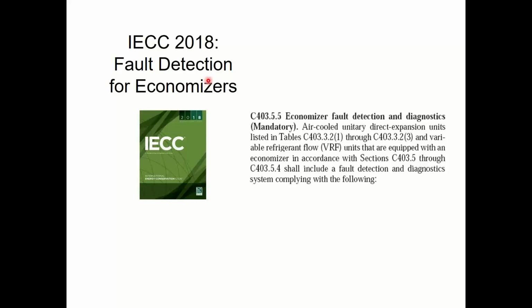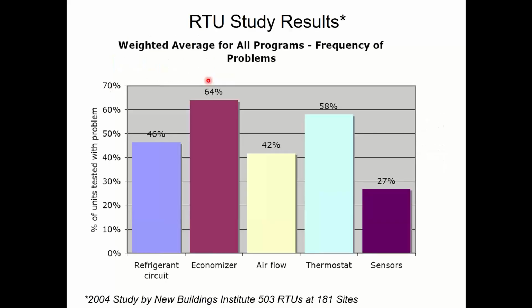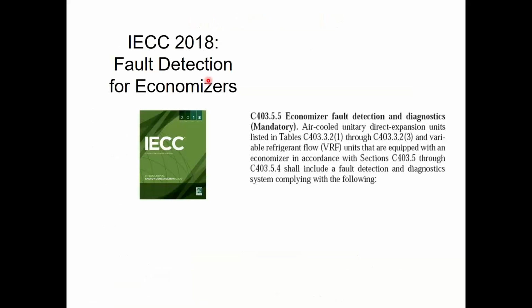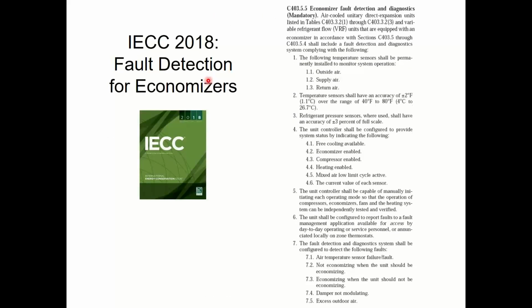The newer versions of the code coming out have even more FDD things, but economizers are the very first one to get it because economizers had this chart that said economizers suck. You guys are doing a bad job. So without reading the whole code to you, what it basically says is the economizer controller has to have the ability to babysit itself. It's got to check various things as listed here to verify that they're working or not. And if it's not working, it needs to notify someone. So for right now, just know that like a Belimo Zip economizer controller or a Honeywell Jade economizer controller does all these various different things.